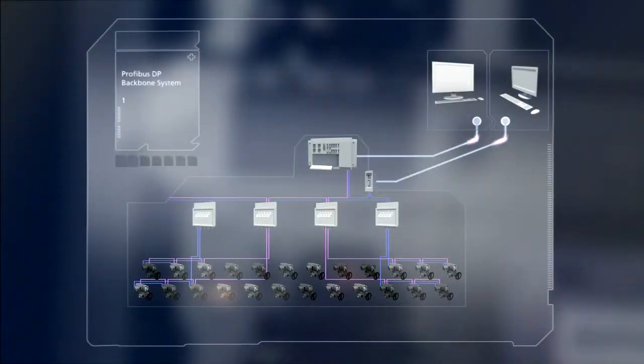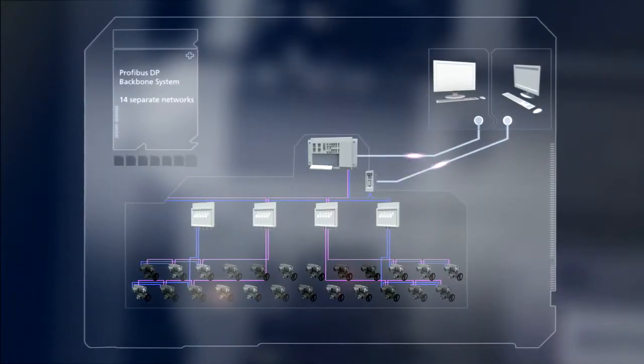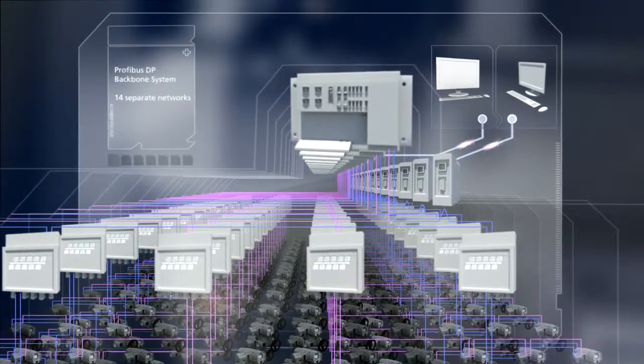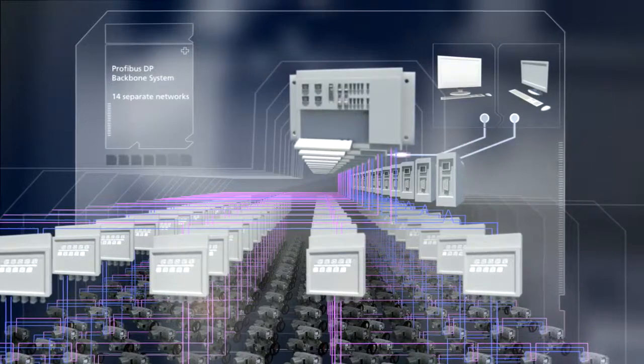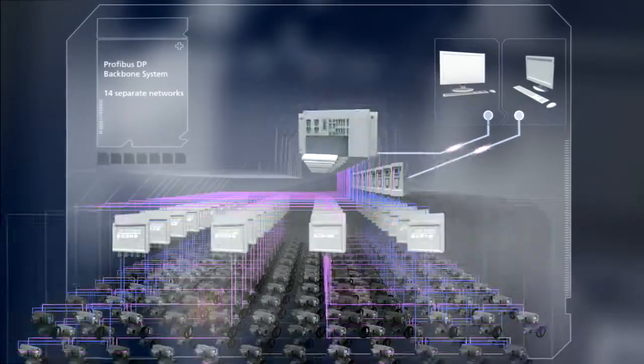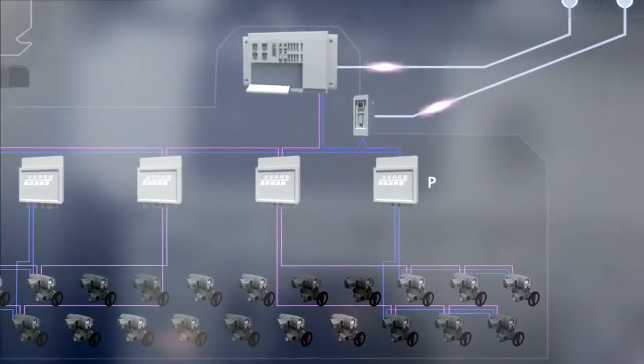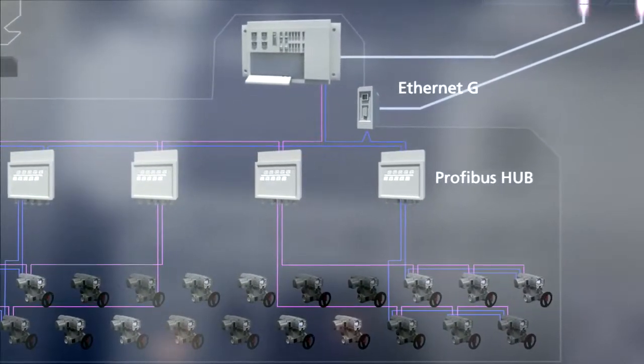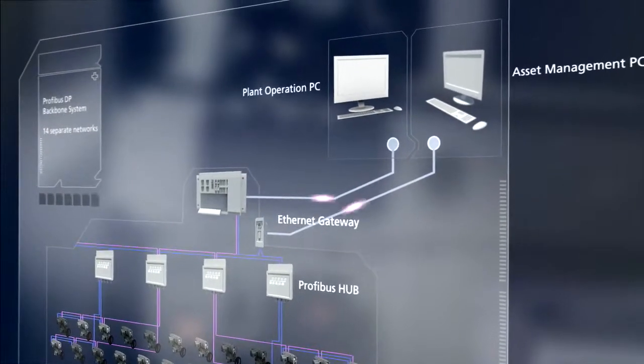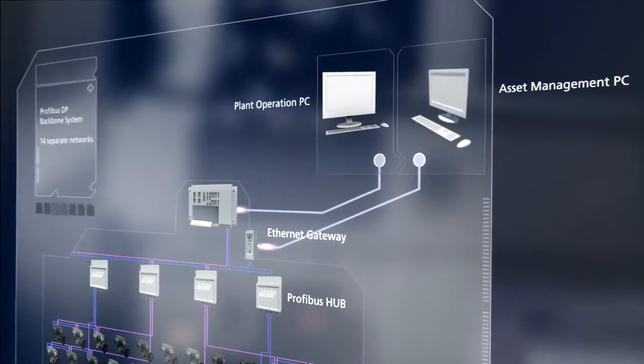The solution is based on a PROFIBUS DP backbone system and comprises 14 separate networks. Each network segment works autonomously and is protected against any impact occurring at other locations. Actuator information is converted via PROFIBUS hubs and Ethernet gateways and is connected to the PC for asset management by means of standard network cables.